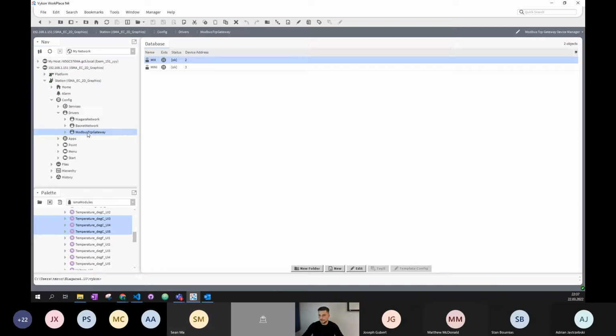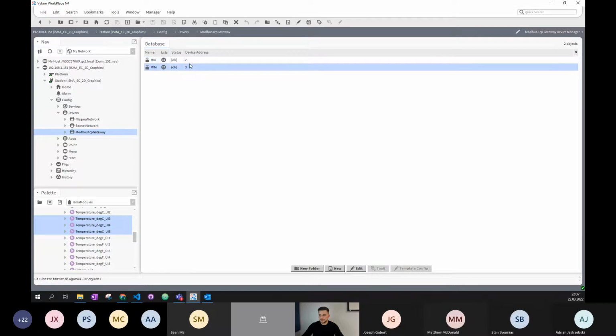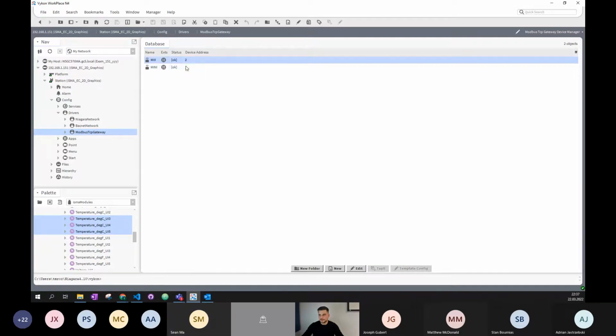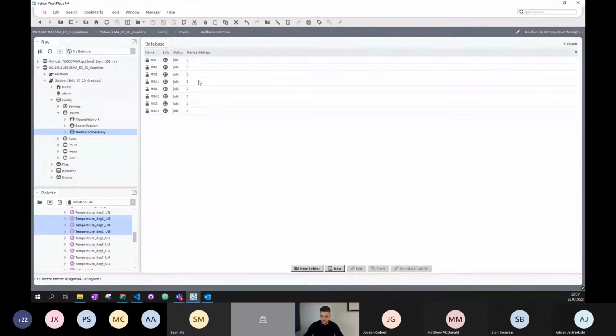This way, I'm just creating one socket here on the Modbus TCP gateway level, and then I can have many more devices integrated without worrying about open sockets. So this is the optimal approach when using the Modbus TCP gateway in Niagara.